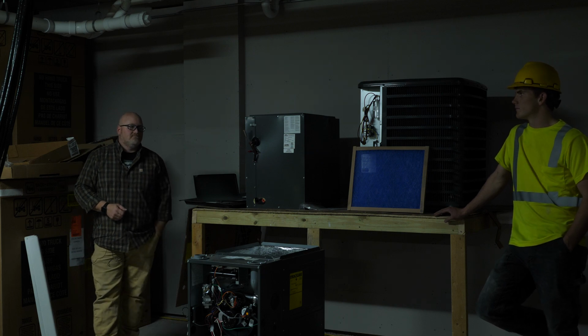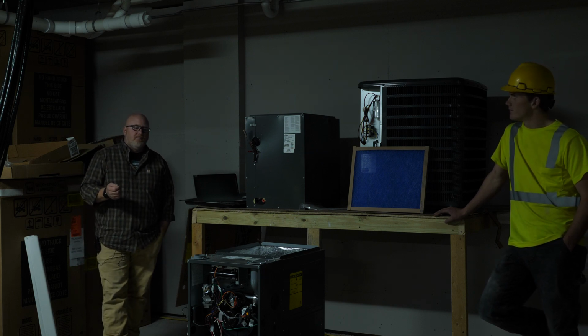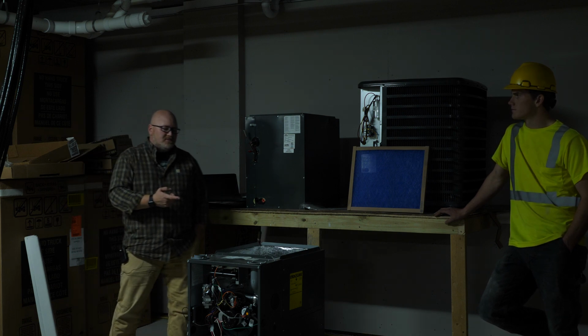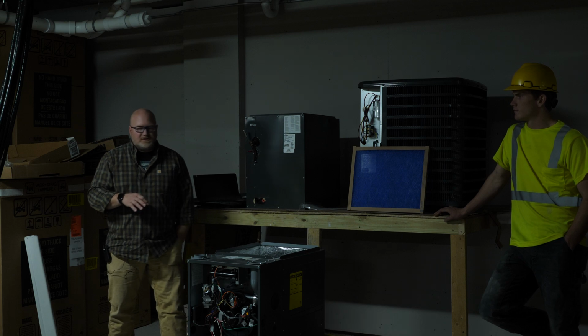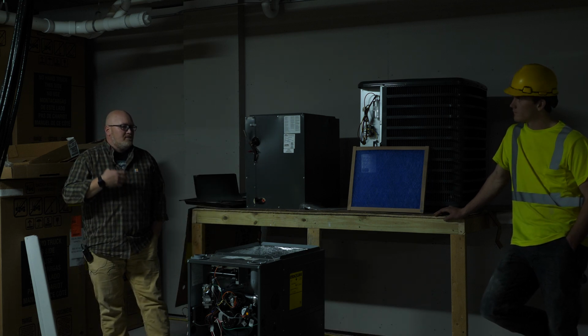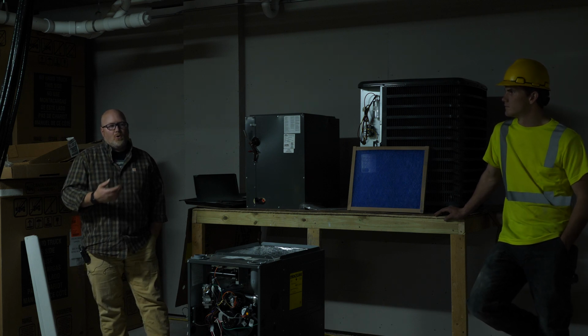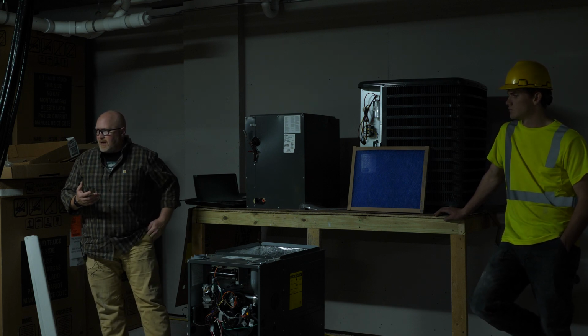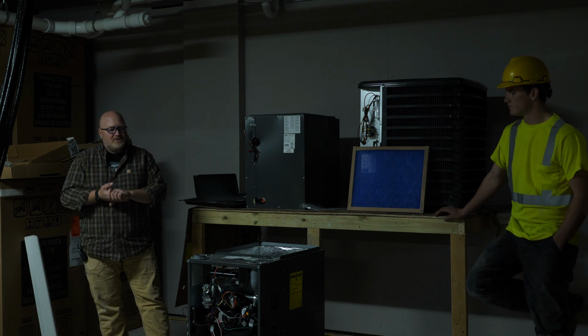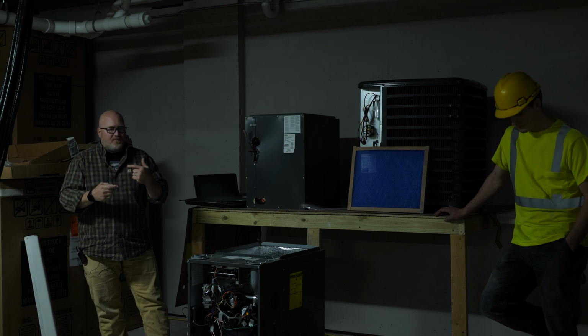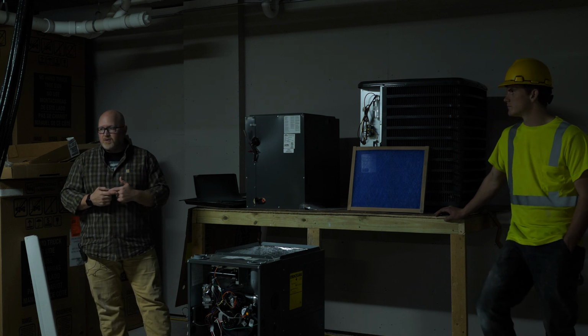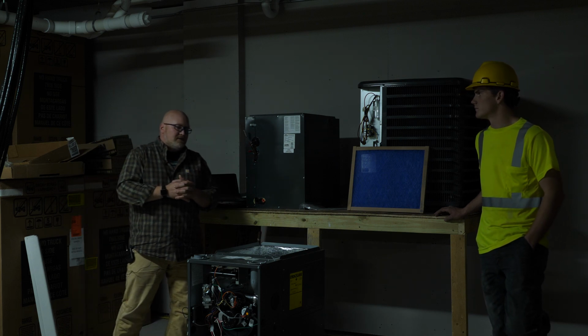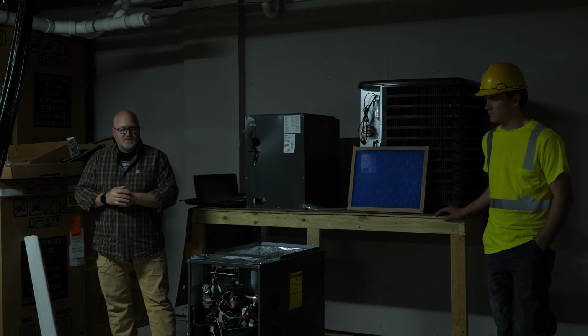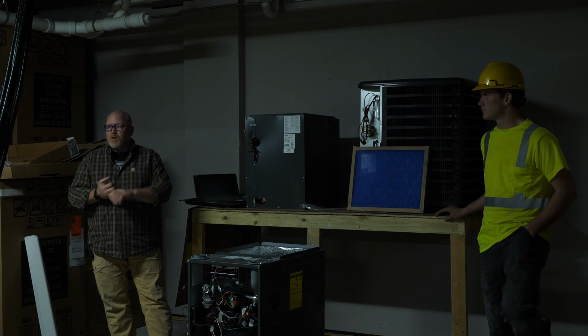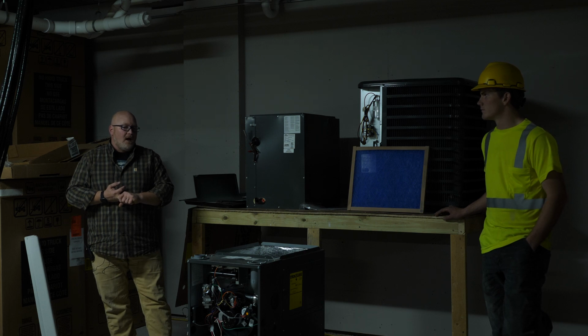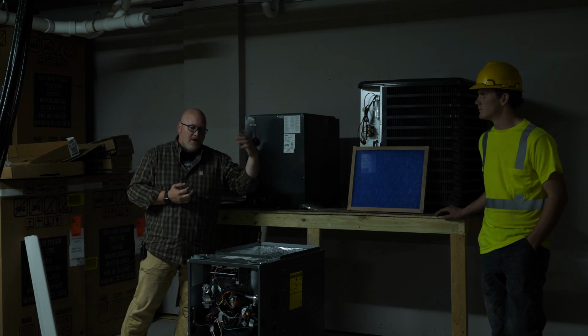Another thing that's important for people to understand is that the newer furnaces are designed to run a lot more often and longer than your older systems. With the technology out there today, with the ECM fan motors, electronically commutated motors, they're going to run about 75% more efficiently than a split capacitor motor. I know this is getting a little technical, but just know that on most newer furnaces, that fan motor is going to run longer, run more often, and be quieter, so you're not going to hear it. But what that means is it's circulating much more air through that filter.